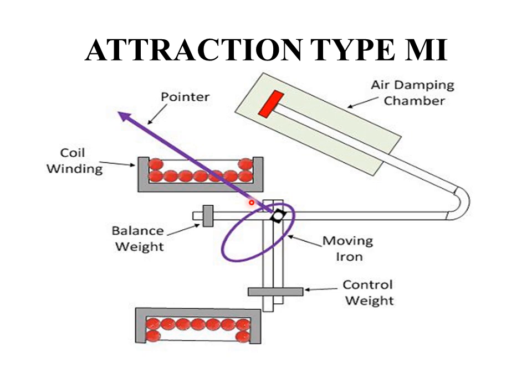This is the construction of an attraction type moving iron instrument. Here there are stationary coil windings and an iron core, which is the moving part — hence this type is known as the moving iron instrument. The iron core is in the shape of a flat disc. When current flows through the coil it creates a magnetic field, and because of this magnetic field the iron gets attracted towards it.